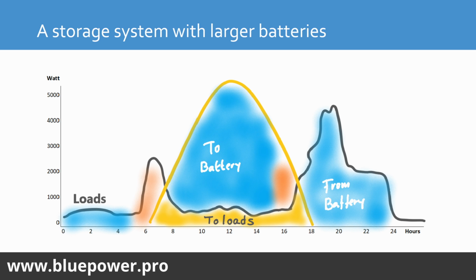Sorry, you only have your PV connected to a SmartSolar MPPT charger, right? And you don't have the grid tie inverter or the AC coupling on this side for your non-essential loads, right? But the essential loads are connected. You still require that energy meter? So that's not a requirement, is that what you said? Yeah, not a requirement. Only if you want to feed non-essentials with excess solar power, then you require the energy meter.